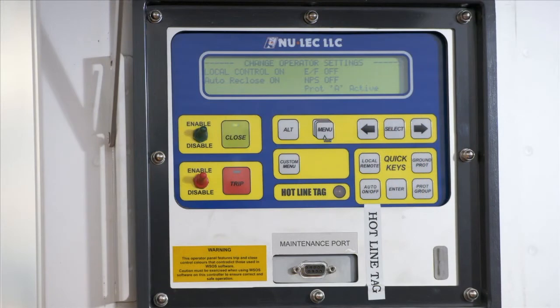The following descriptions outline the operation of the various elements in the SetView operator interface. Display: backlit LCD screen with 4 lines and 40 characters per line. Left scroll key selects the previous screen in a display group, or if a setting is selected, decreases its value. Select key. Press to select a data field or setting so that it can be changed. Right scroll key. Select the next screen in a display group, or if a setting is selected, increase its value.